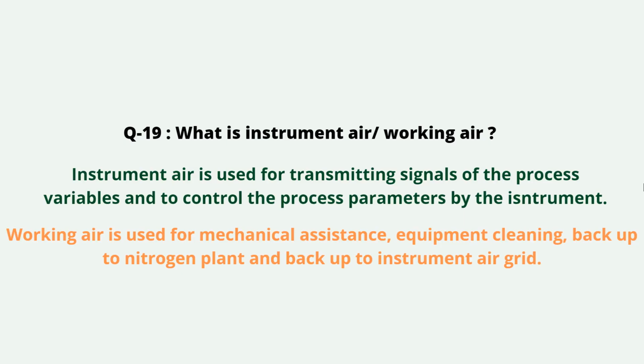What is instrument air? Working air. Instrument air is used for transmitting signals of the process variables and for controlling the process parameters by the instruments. Working air is used for mechanical assistance, equipment cleaning, backup to the nitrogen plant and backup to the instrument air grid.